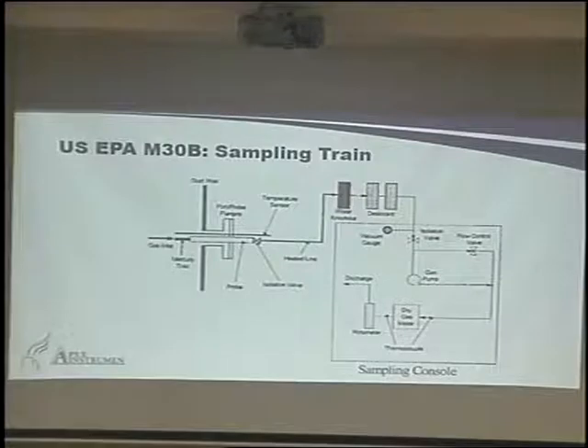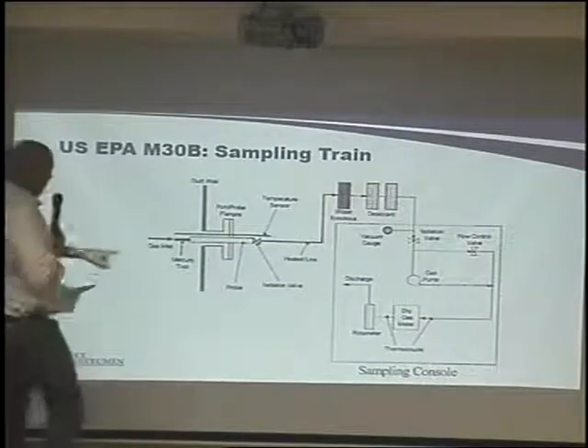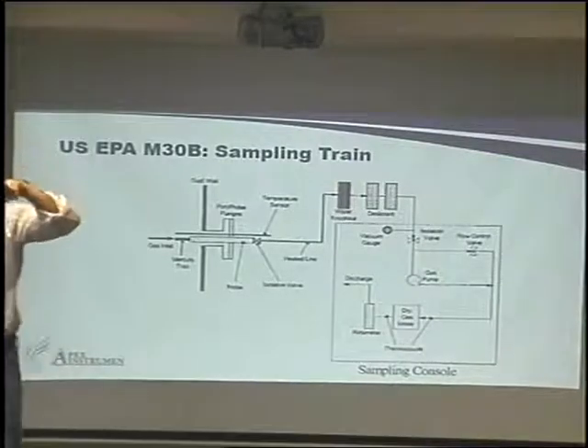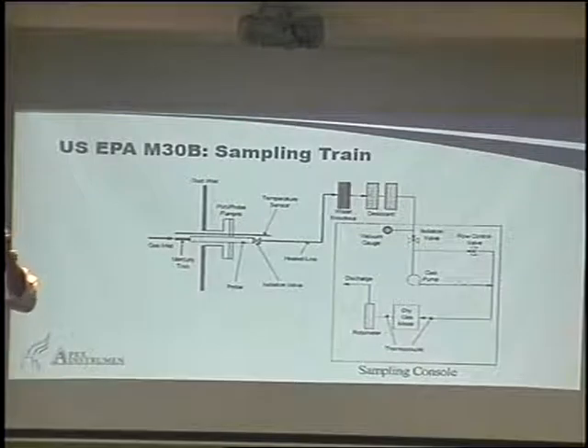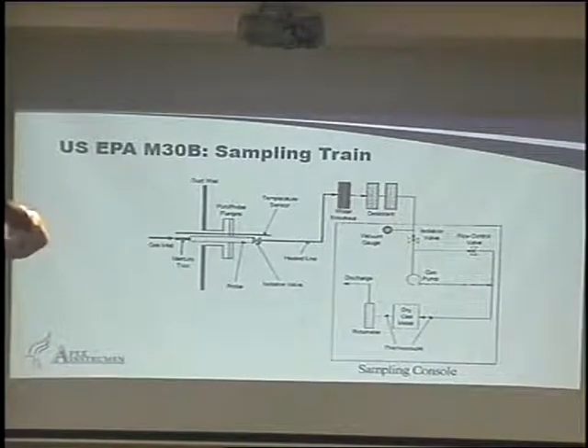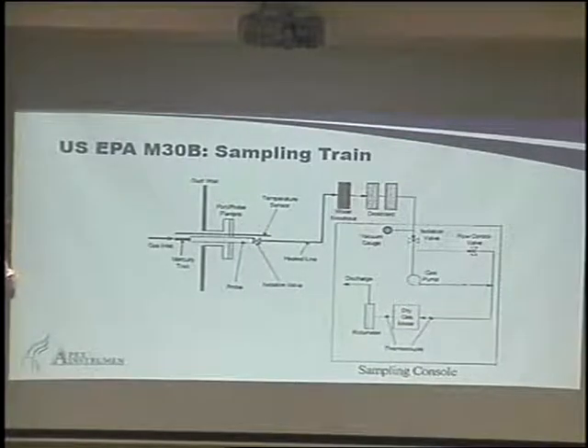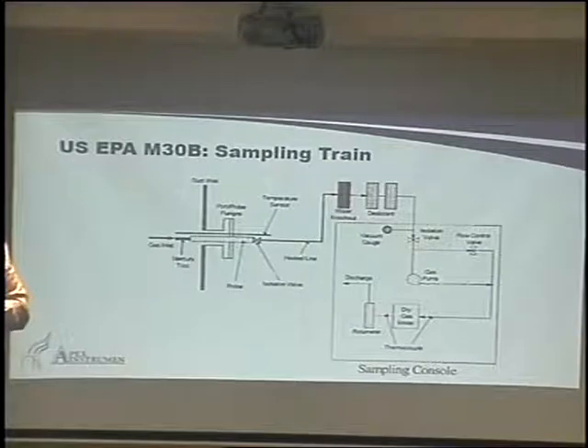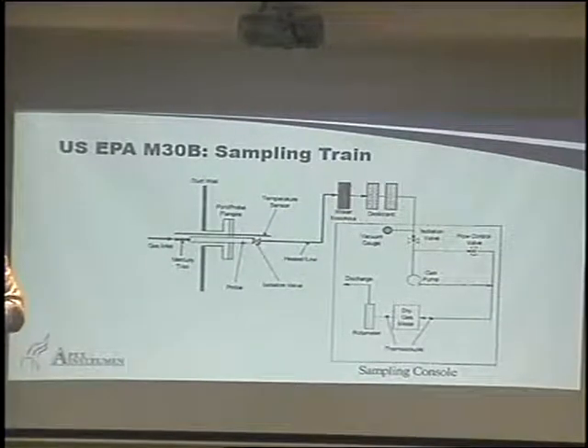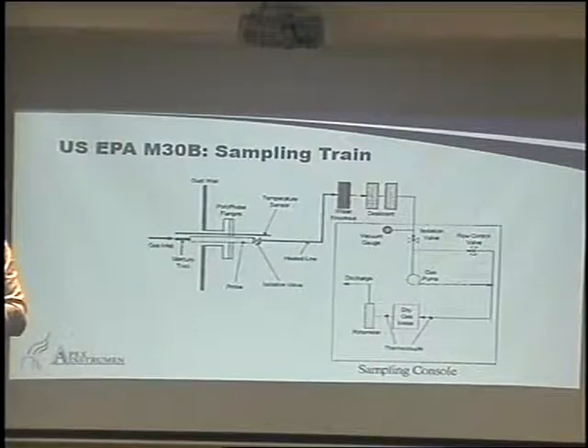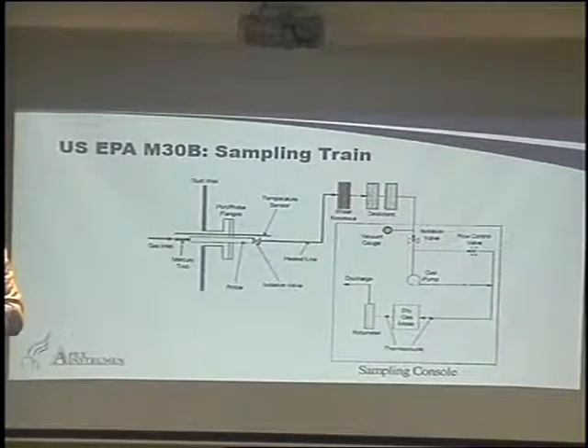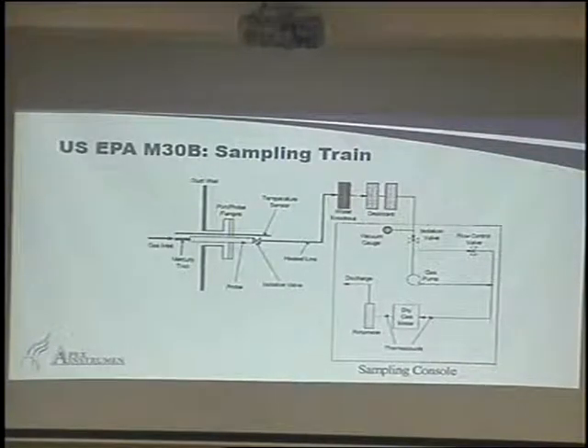So this is the schematic as it is shown in the regulation in the US, exactly, okay? So right here, we have our 2 sorbent traps that go in the front of the probe. And a sorbent trap is about 30 centimeters long and about 10 millimeters in width, okay? And it has either 2 or 3 beds of carbon, sections of carbon, separated by a small filter between each one, okay? Then at the back, the glassware comes down into a point, and the gas will go through the probe, through your sample line, and make its way to your console, your instrument, where you're going to be reading your operation.